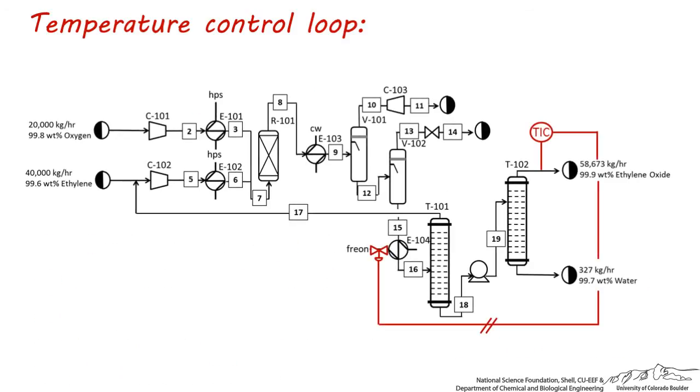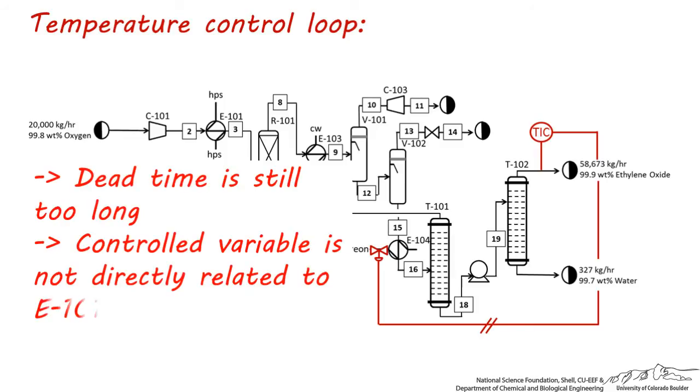Let's look at another example. This is another way of trying to control T102's distillate temperature. What might be wrong with this loop? This is also a bad idea, since even this heat exchanger is too far away from the final product stream. There's still at least a 10 minute dead time in this loop. Also, the distillate temperature is not directly related to this heat exchanger.